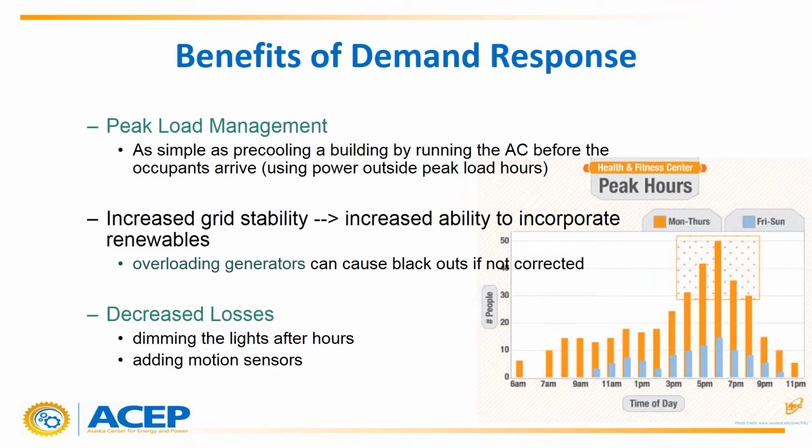Demand response can also increase grid stability by controlling which loads are dropped in the event of generator overloading and a reduction in frequency of the power generated. If you think of a generator as a car driving uphill in a high gear and the grade of the road as the amount of power being pulled by the connected components, then direct load control allows for a fast reduction in steepness of the road so that the car continues after slowing down rather than stalling out on the hill. In the case of a diesel-electric generator, sustained overloading will result in a blackout.